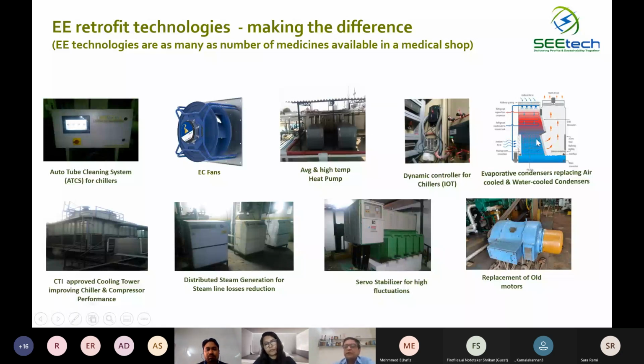Then this is a conceptual picture of the evaporative condenser. In an evaporative condenser, your condenser and cooling tower are all brought into one particular piece of equipment. Even if you change a water cooled condenser to an evaporative condenser, you save energy on the compressor as well as the pumping power. And when you replace an air cooled condenser with the evaporative condenser, you are going to save a significantly high amount. All these kinds of technologies require a very good amount of competence to implement the project.